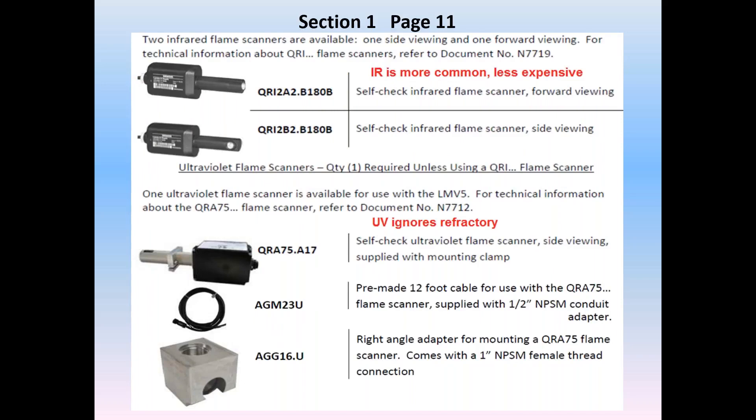Flame detection options include basic flame rod input, IR or infrared scanners, QRI shown here with self-check, built-in amplifiers, forward or side viewing options. Infrared is the lowest cost, most commonly used scanner.